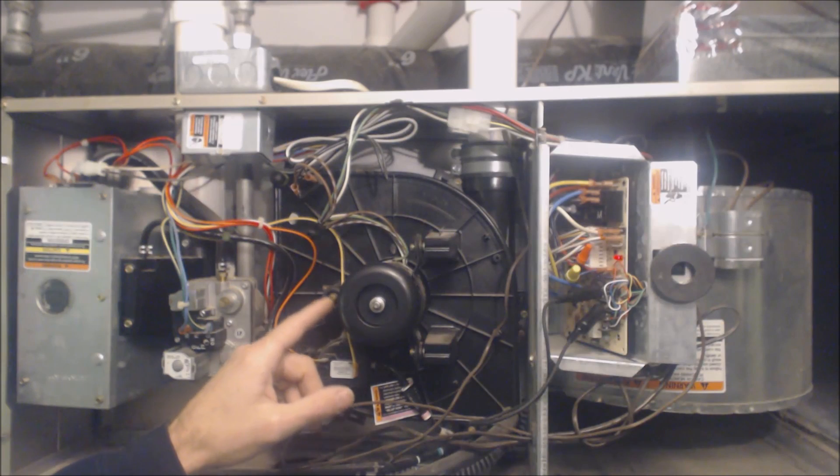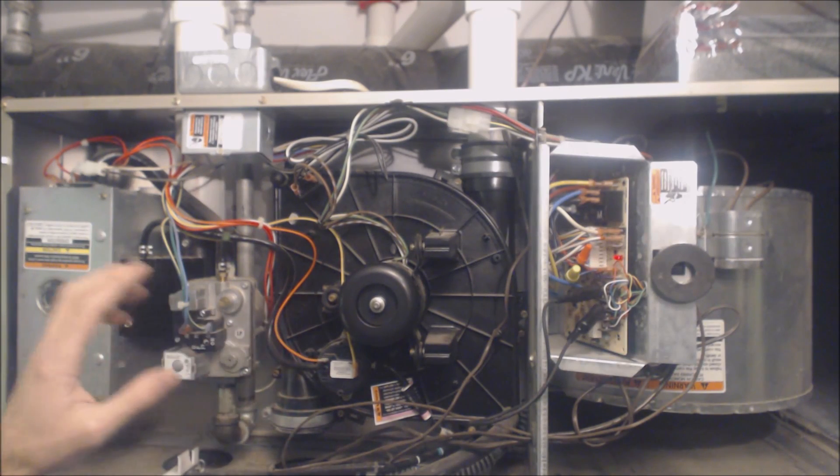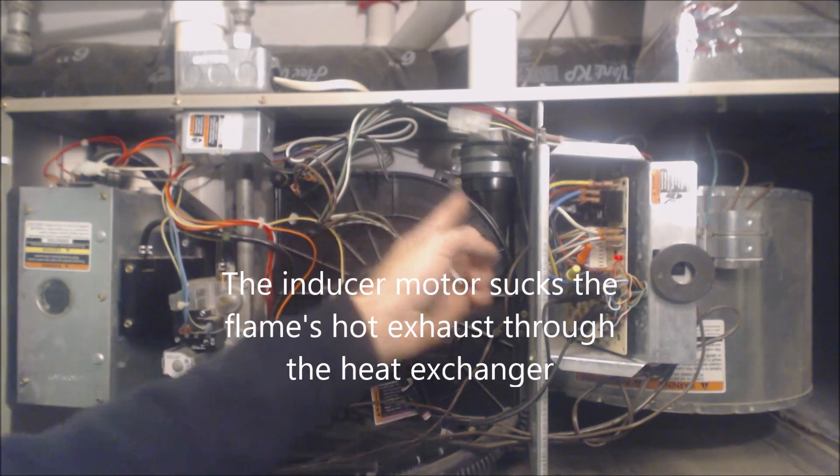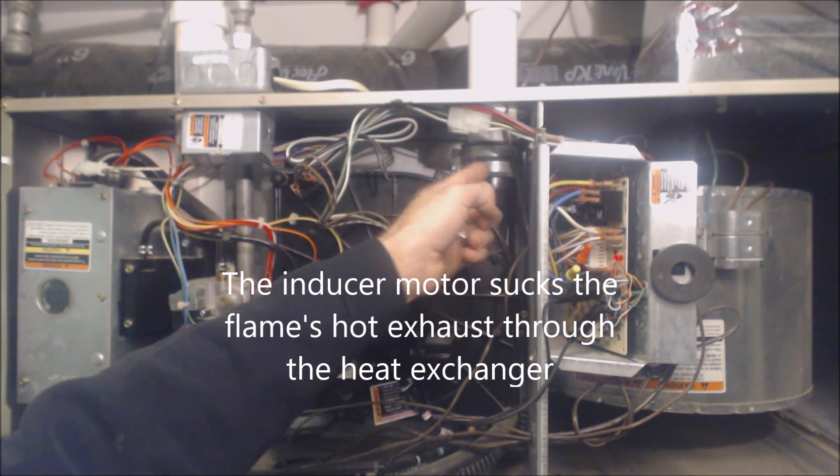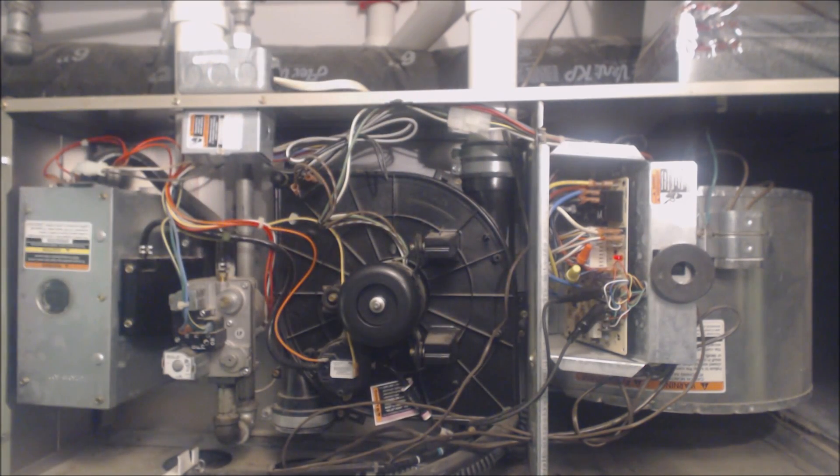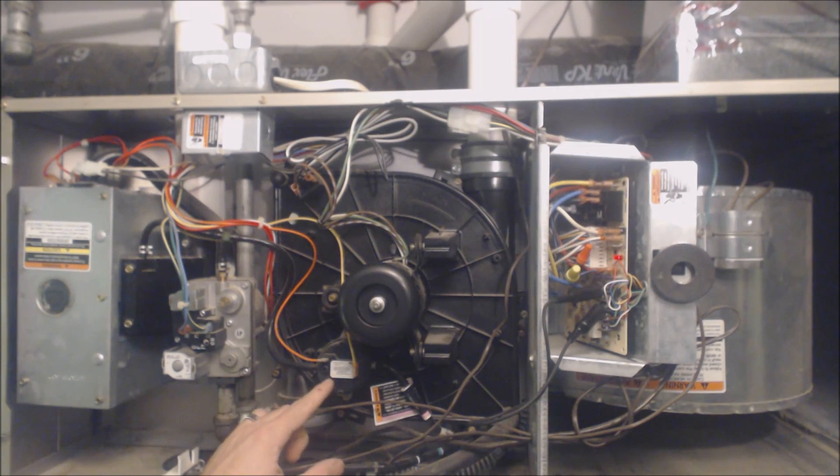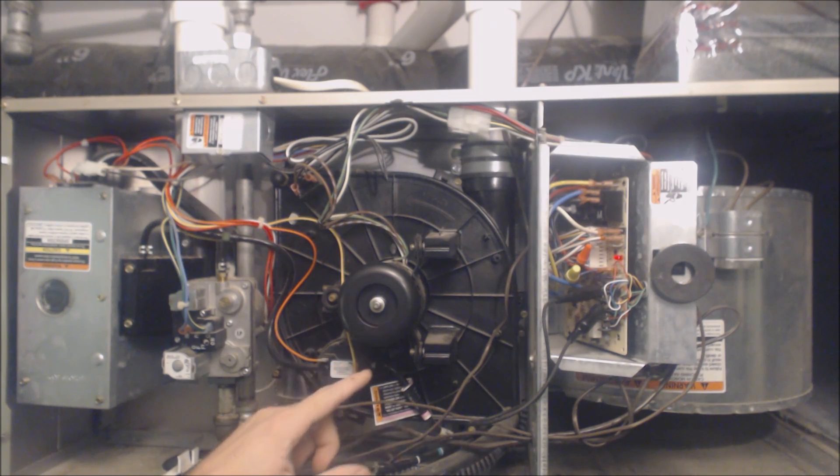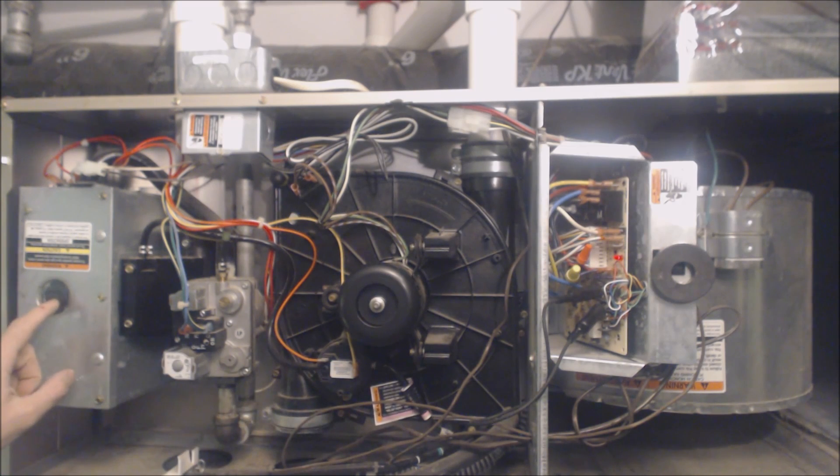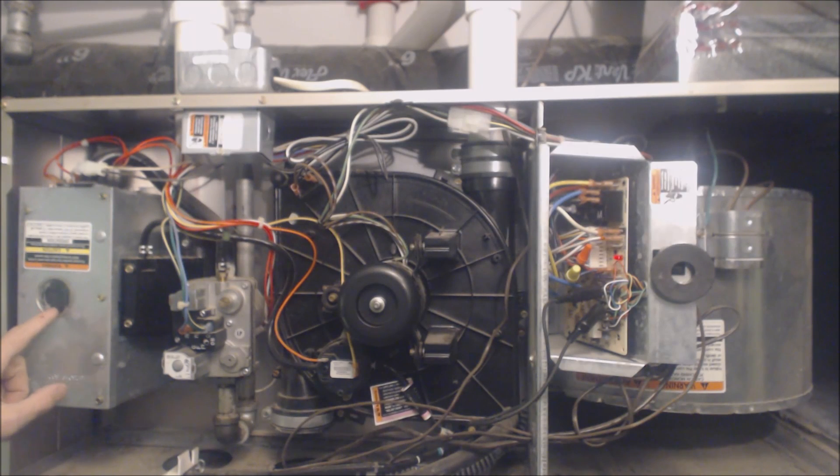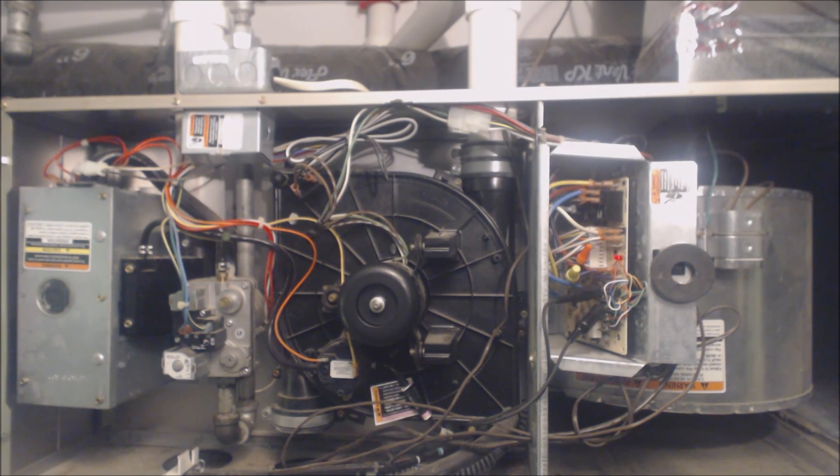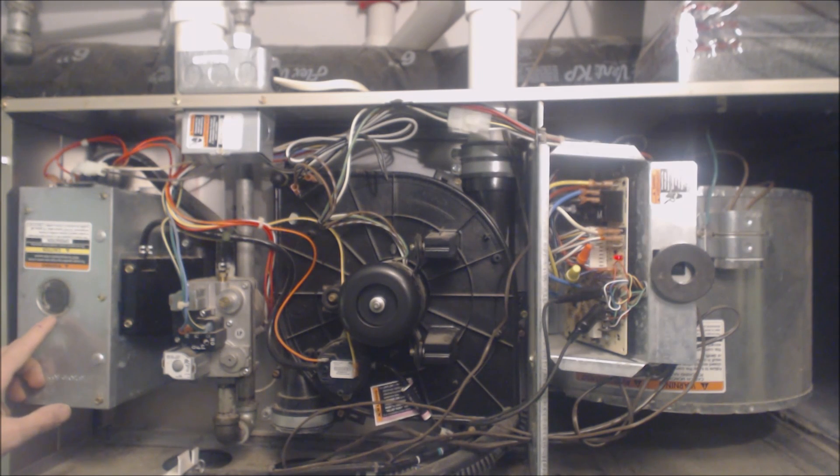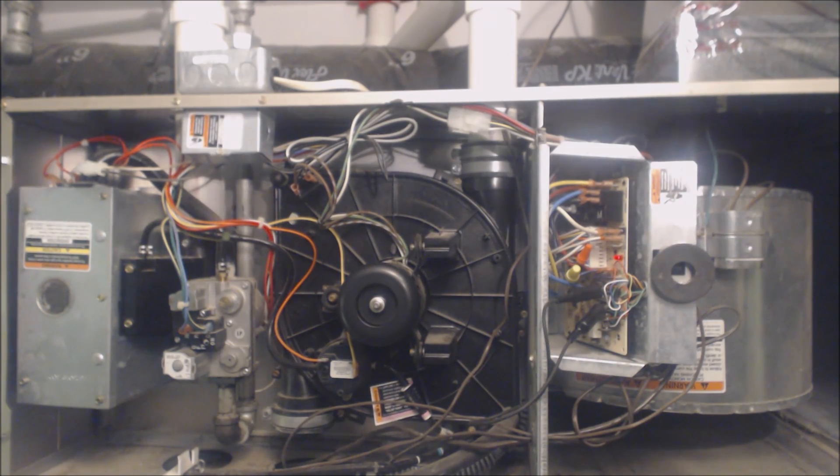What that does is it actually sucks the flames through the heat exchanger and then it pushes it out through the PVC pipe. This is going to run first and then the pressure switch is going to electrically close proving that the inducer motor is actually running. After that, you're going to see orange through this little glass hole here and that is the hot surface igniter. The hot surface igniter has to turn cherry red in order for this to ignite. I'm going to turn this light off so you can see it.